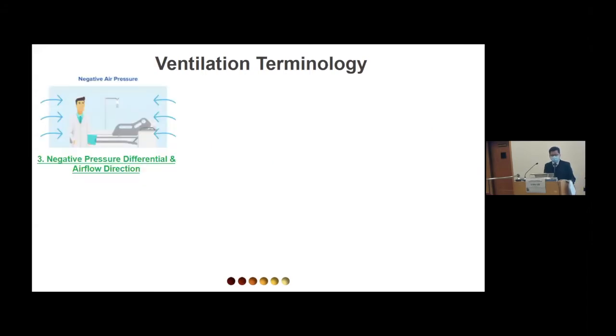Next are the terms negative pressure differential and airflow direction. These terms are commonly used for healthcare premises, isolation facilities in particular, to indicate pressure inside the room with respect to its surroundings. Smoke tests are generally carried out to verify whether the ventilation system has achieved its desired flow direction. Most physicians are familiar with the terms clean zone and dirty zone, as the setup of the clinical facilities requires looking into the workflow to avoid cross-contamination.